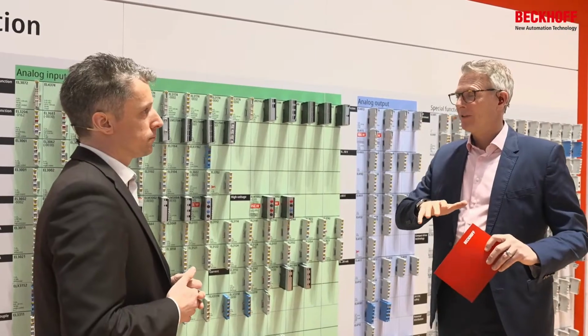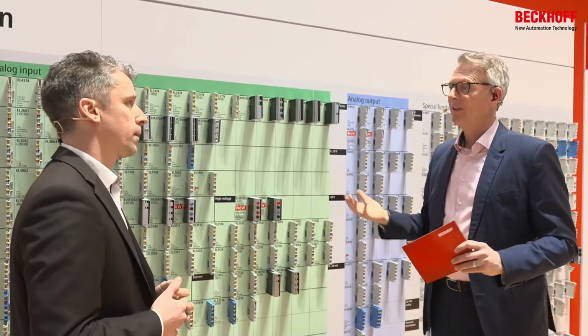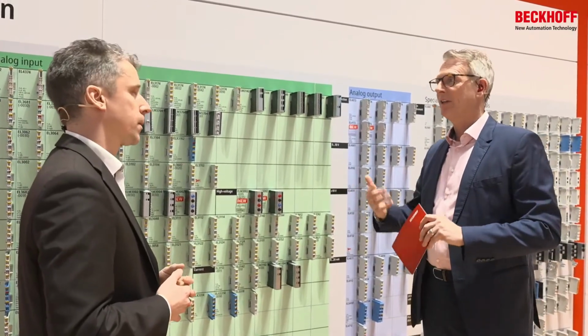The other thing is the current. Now, current can differ from a few milliamps to hundreds and thousands of amps, and I think we also have a special program of components to connect the current into the terminals. Exactly. Our current measurement abilities inside the terminal go from 1 amp to 5 amps to 10 amps at the maximum, but 10 amps is way too little for most applications. So you need to transform big currents into small currents, and that is a current transformer.